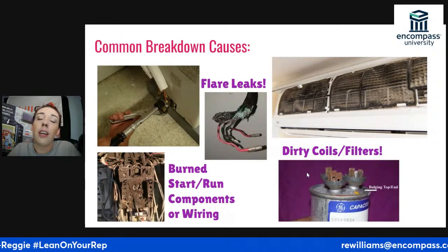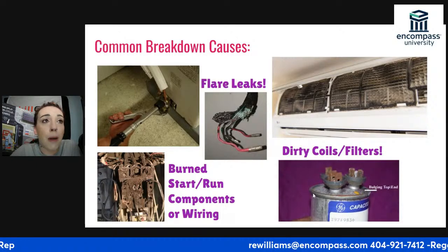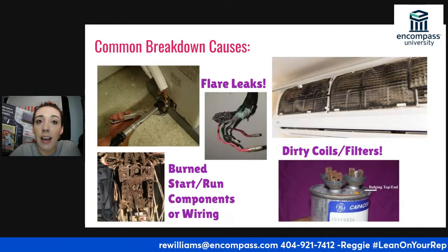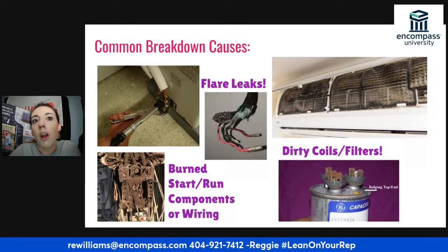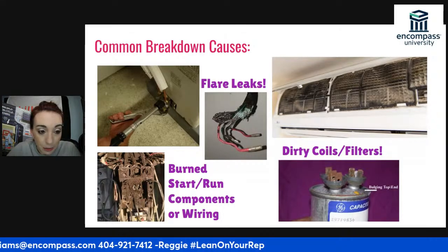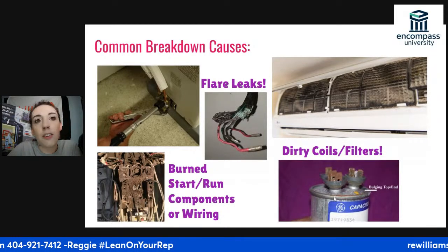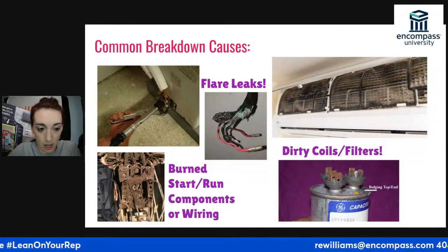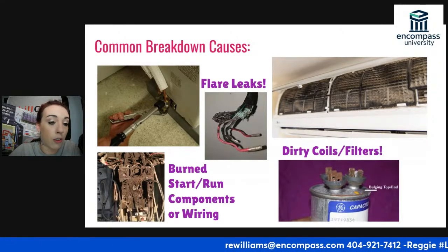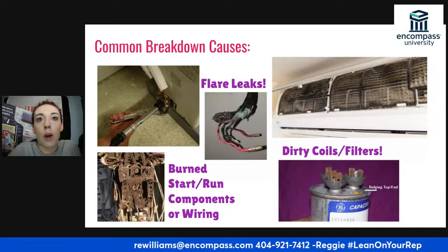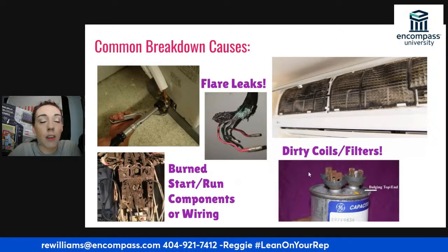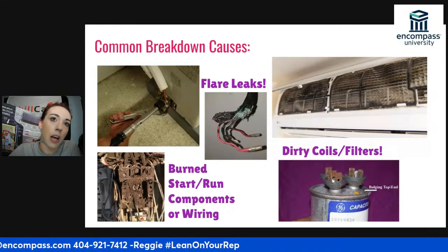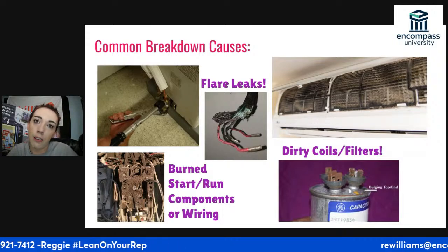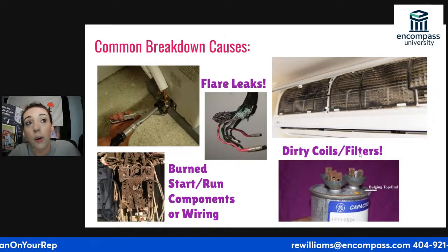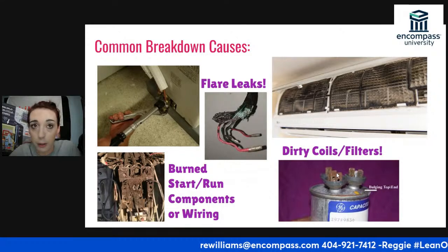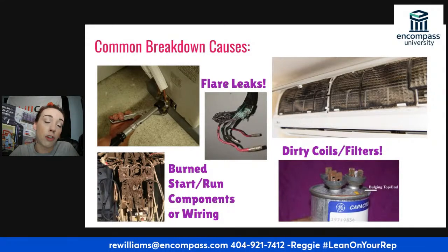The capacitor, let's go with that. Some mini splits have 2, some have 4, some have 1. A capacitor is a capacitor, right? So capacitors hold capacitance. That's what they do. They help the fans to start, and then they help the fans to run without draining a bunch of power directly from the panel. So we wire the fans into these. And then sometimes you'll have the contactor wired to this. Sometimes you'll have this directly wired to the compressor. So sometimes you'll have 2. You'll have 1 for the fan, 1 for the compressor. In mini splits, a lot of the time it's 2 smaller ones.